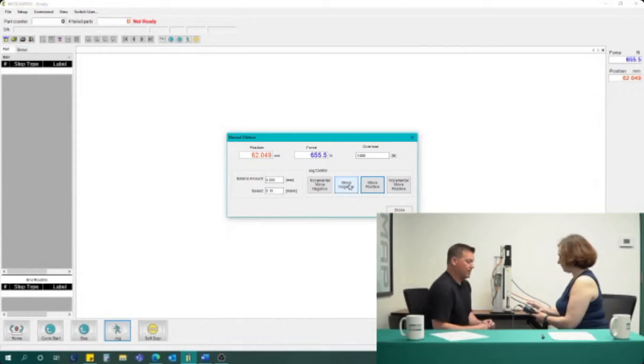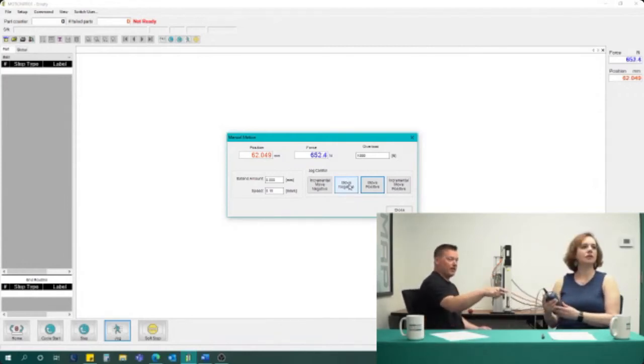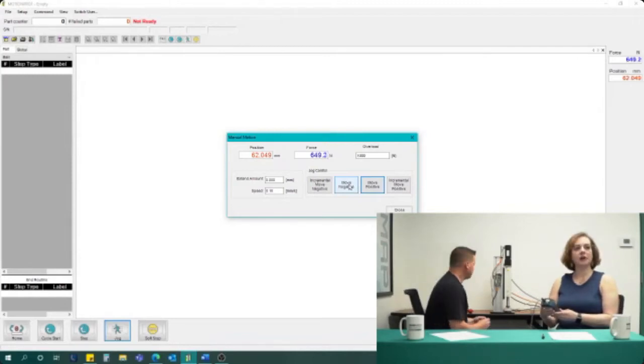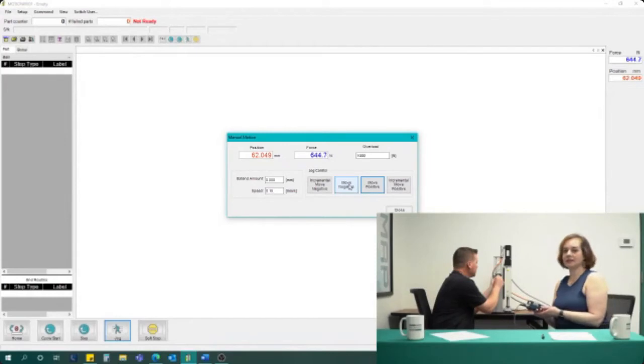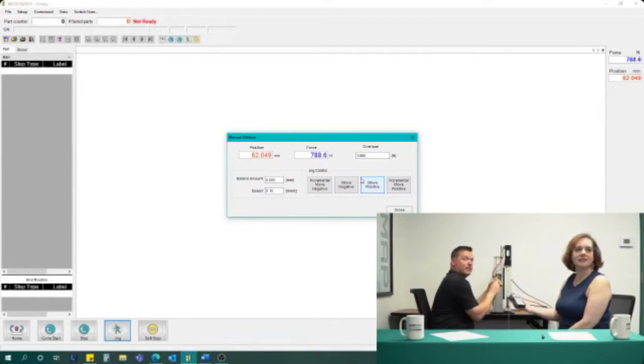And now you can see that we're going to compare the readings from the master load cell meter to the readings you see on the screen. So we are off. We're reading 770 newtons right now, as opposed to the 646 that we see on our readout. So we just need to turn, and there. You're at 765. So now I'm making my adjustments here. And getting close. So this is where human error plays a little bit into this. We're reading 762, and you're a little bit too far.